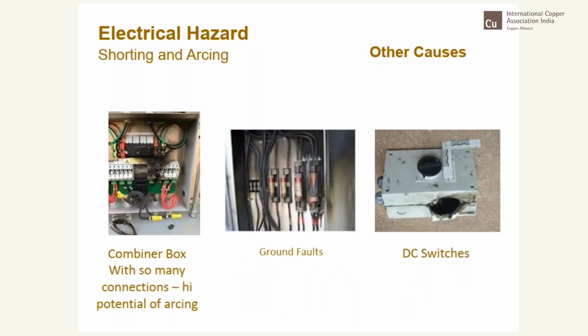Then we have shorting and arcing, a typical example of which was shown by Mr. Sivaram Krishnan again. He also showed the problem in the combiner box. The combiner box is a potential source of fire accidents because so many connections take place and control devices and breakers are there. So this definitely requires extraordinary attention and care, and doing the right thing the first time itself. Otherwise, repairing, locating and changing will create problems. So this needs to be taken care of.